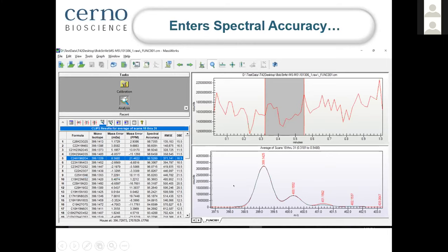You can do better than that, to the number five hit, which gives you a good match on the plus one, indicating the carbon number is very close, but the sulfur number is still off, it's underestimating. And it's not surprising that all top four contain exactly one sulfur, and the correct answer is indeed in the top four. You can tell number three is not the right answer because the carbon number is off. Between the top one and two, we can't really tell the difference because the spectral accuracy is 98.7 versus 98.6, but we can narrow it down to the top two from a total of 61 candidates.